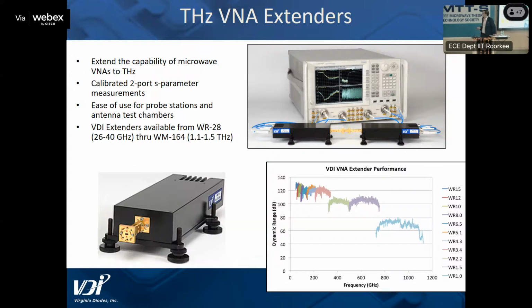And this seems a little funny at first that we have extenders. To me, 26 to 40 gigahertz seems like a very low frequency to have a frequency extender, because you could have the network analyzer itself measure over coax at 40 gigahertz. But there's an interesting use case for why you would not want to do that, and that's in antenna test chambers, where you might have a very long, say 5 or 10 meter distance between your base unit, your network analyzer, and your actual device under test.